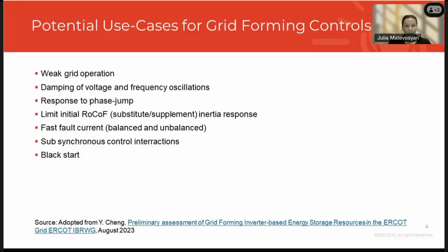So potential uses for grid forming control so far that we see are operation in weak grid, damping of voltage and frequency oscillations, response to phase jump, and limiting initial RoCoF. So you can see it as supplementation or substitution of inertia. But basically the main idea is to limit rate of change of frequency after a disturbance event on the grid. Also fast fault current injection, subsynchronous control interactions mitigation, and black start in some cases.